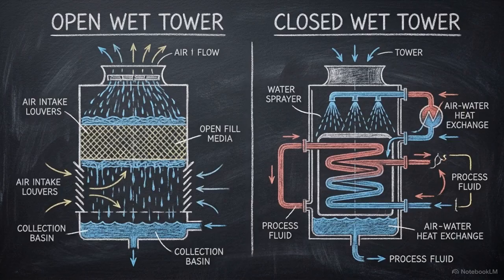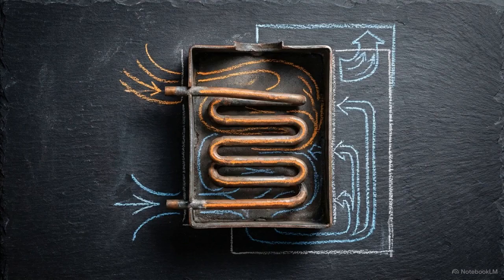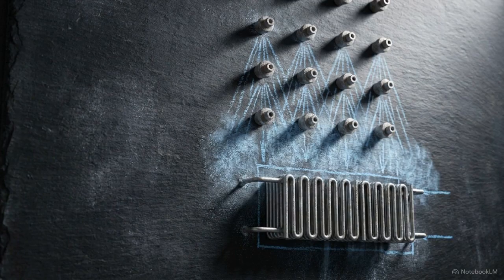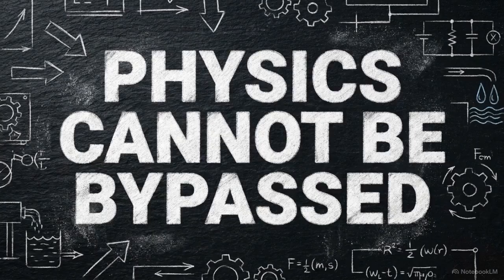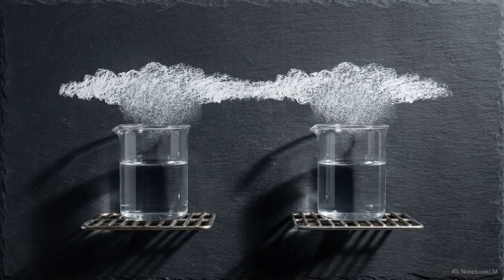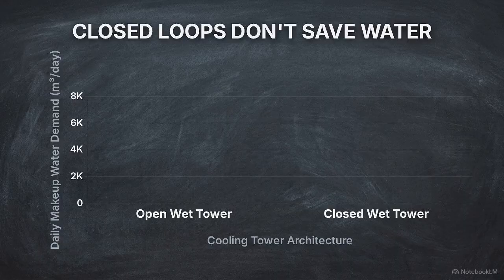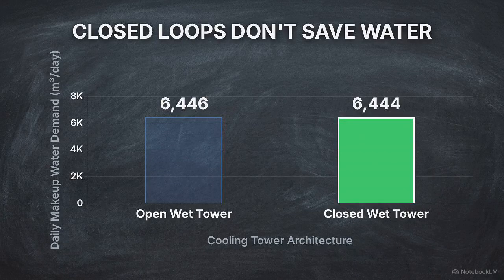We can now compare this to a common industry assumption, that transitioning to a closed-circuit wet tower inherently reduces site water consumption. In a closed-circuit tower, the facility water stays protected inside a coil, while a separate spray loop wets the outside of that coil. However, the latent heat of vaporization remains a fixed physical property. To reject 151.6 megawatts, the system still dictates evaporating the exact same mass of water. The data shows that a closed wet tower demands 6,444 cubic meters daily.